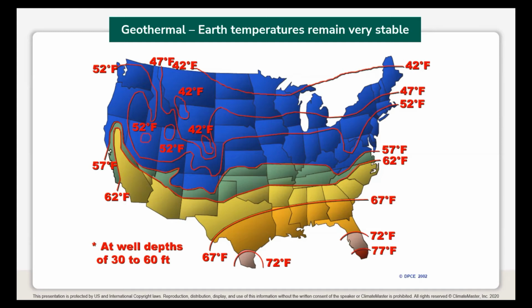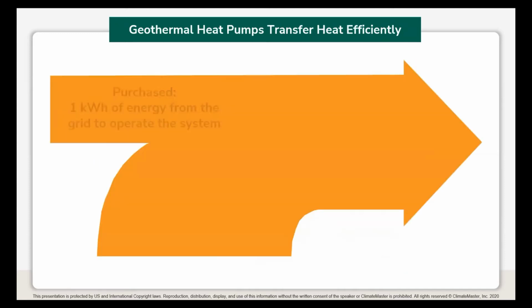If we were able to use an air source heat pump with constant temperatures of 45 to 52, you would have a very efficient product. Unfortunately, Mother Earth doesn't cooperate with us, and we see outdoor temperatures that go into the 90s or drop down into the minuses in many areas of the country.